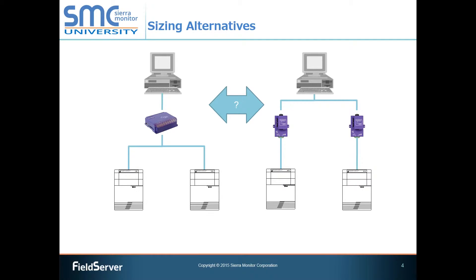Sometimes the application forces you to use one hardware platform with one connection to the network. This is typical in serial protocol applications, especially RS-232 where point-to-point communication is mandated. However, if this is not an issue, then one would have to consider the usefulness of splitting data between multiple field servers for larger applications. While it is typically slightly more expensive to have two smaller field servers do the job of one larger one, there are inherent benefits relating to physical positioning of gateways and usually an increased speed of communication brought about by using multiple communication ports and processes instead of one.